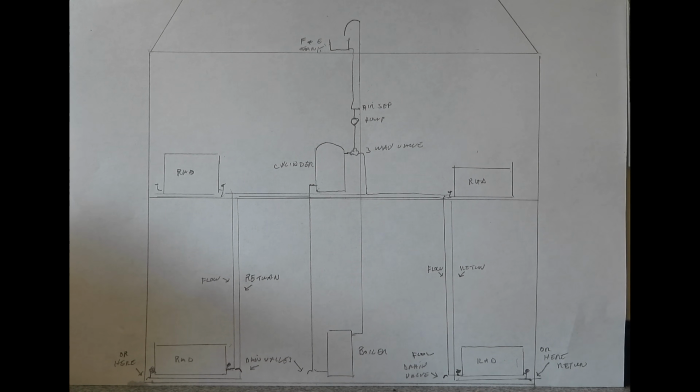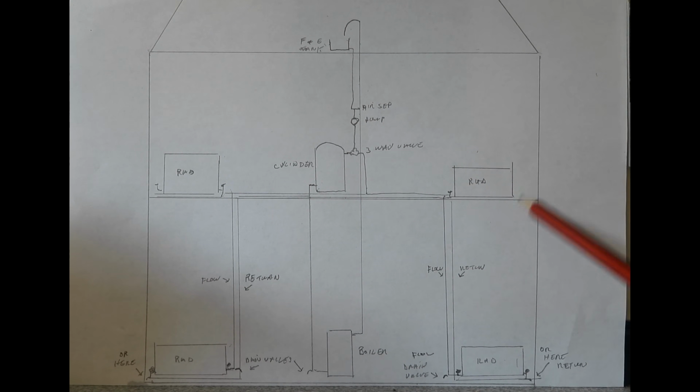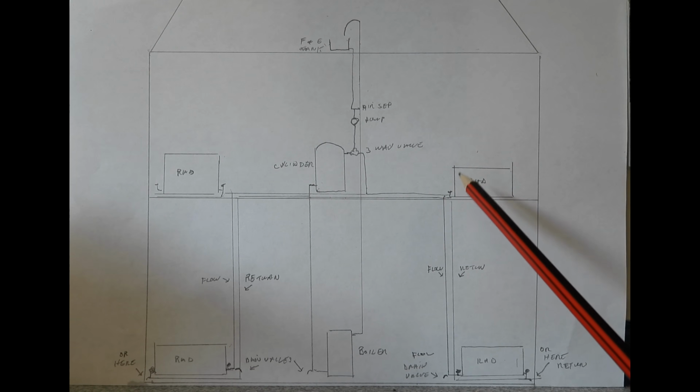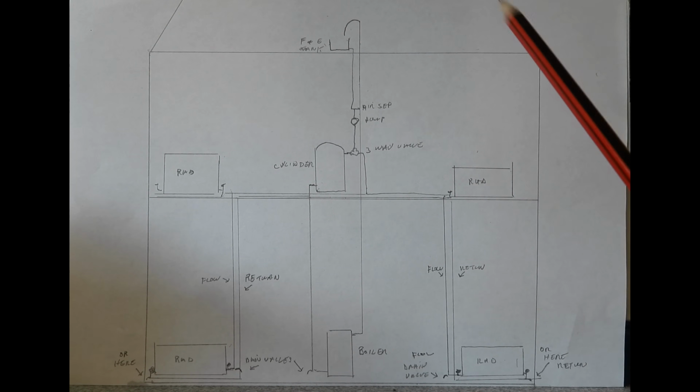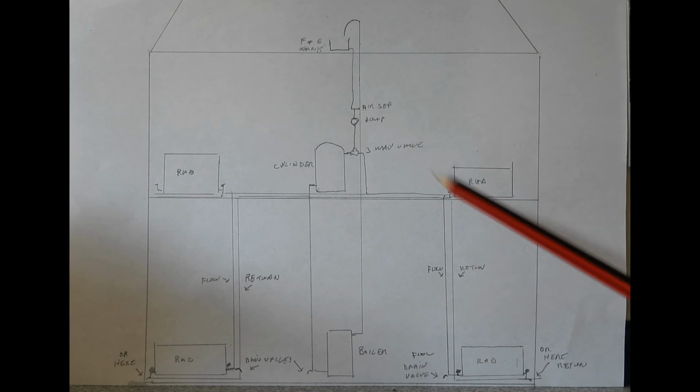And also the problem is when you fill up, the system all fills up okay, but you quite often find it gets air in these drops just before the drop goes down here. You might get one all right, but then find that there's an odd one that doesn't go, and that's when the problems begin, because quite often you get an air lock here. And the only way you can probably get that out, you can try turning all the radiators off except for the one that isn't going. We'll say it's this one, and that usually does it.